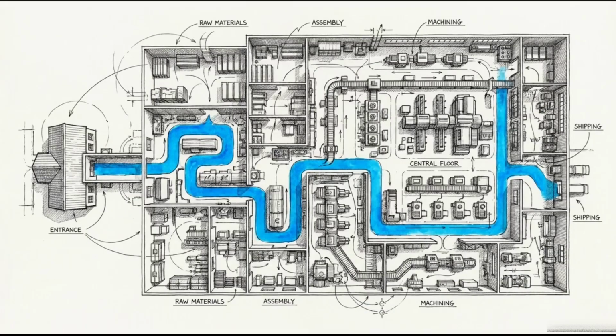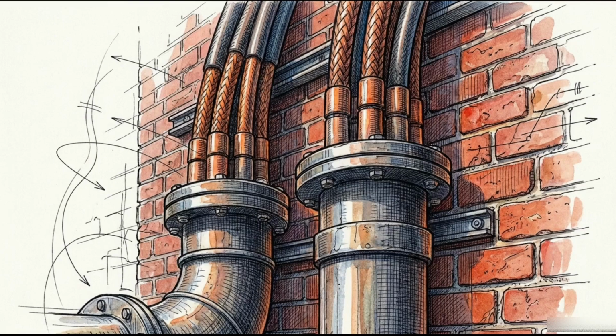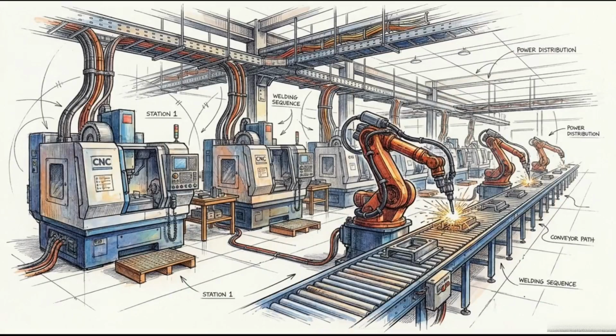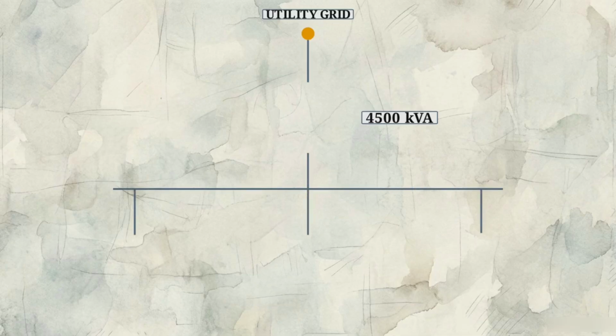Auditing a plant requires mapping the entire journey of that electricity, from the high-voltage utility entry down through step-down transformers, and finally into the diverse loads of the factory floor. This single-line diagram illustrates the plant's primary bottleneck. Raw utility power enters a step-down transformer with a fixed capacity of 4,500 kVA. However, there is a discrepancy between the transformer's capacity and the machines it serves. The transformer provides total power, but the heavy inductive motors on the line consume specific active loads, such as these 22 and 50 kilowatt units.